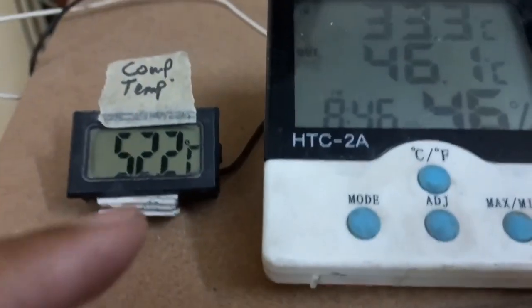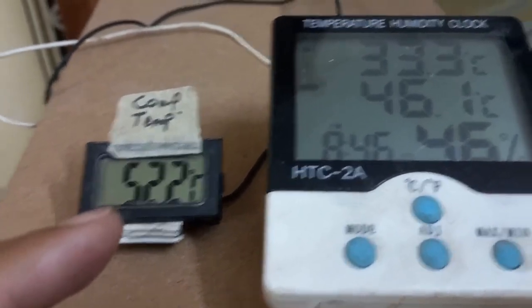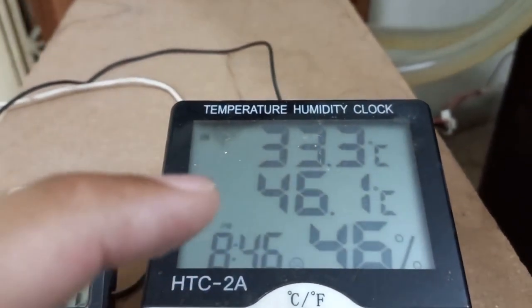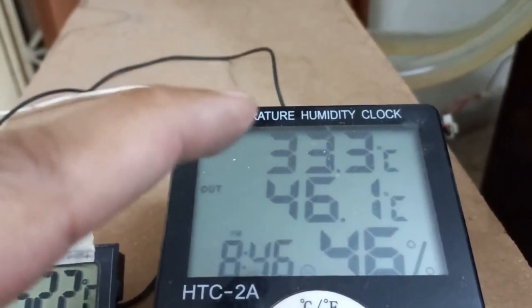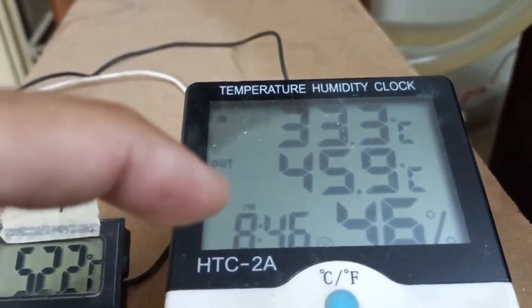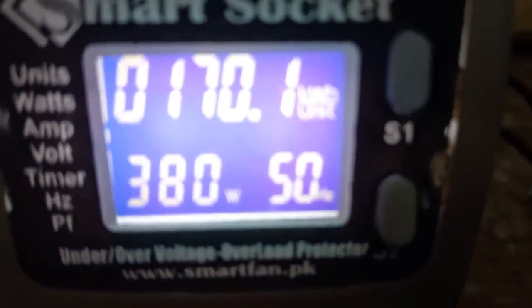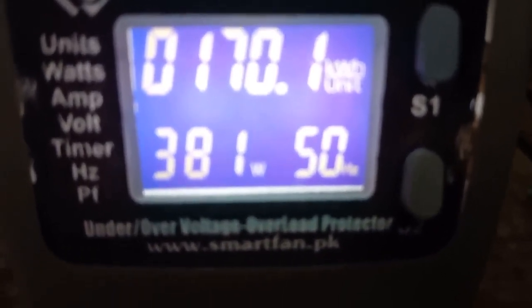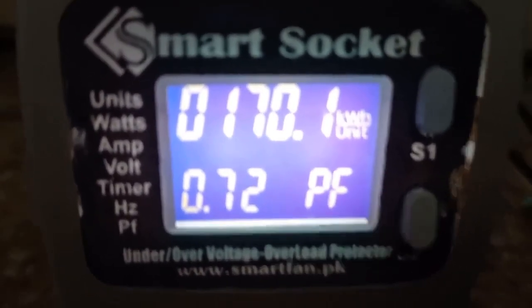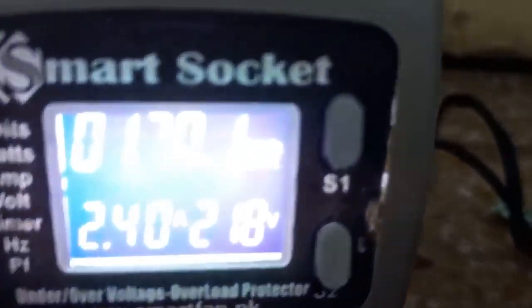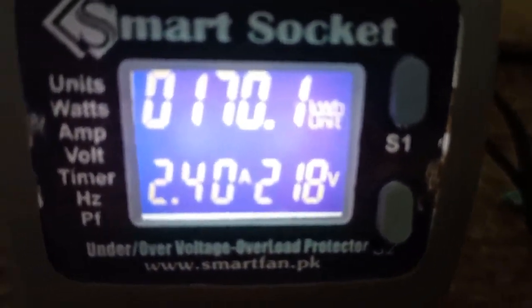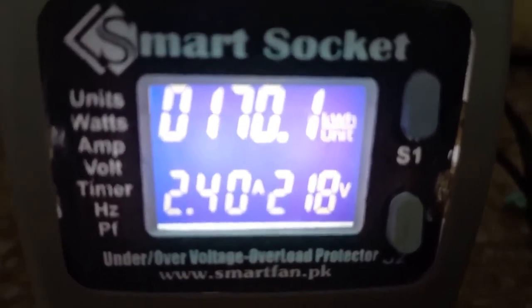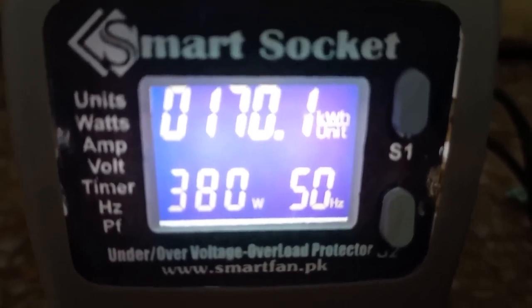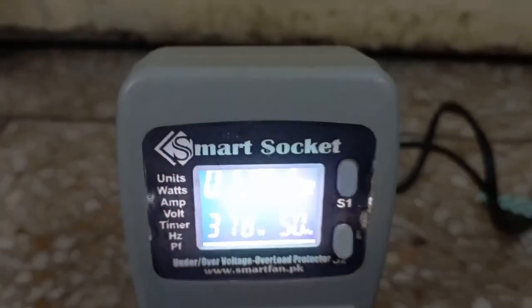Here the temperature is 52 degrees compressor temperature and 46 degrees condenser temperature, and ambient temperature is the same as before, 33. Now the time is 8:46 pm because the fitting took too much time, as the fitting was a little bit different. Now if I check on this meter, same current as before, 2.4 ampere, 380 watt, and power factor 0.72, same as before. The current should be a little bit more due to this big fan, but it's the same as before. Wattage also 380 like before.